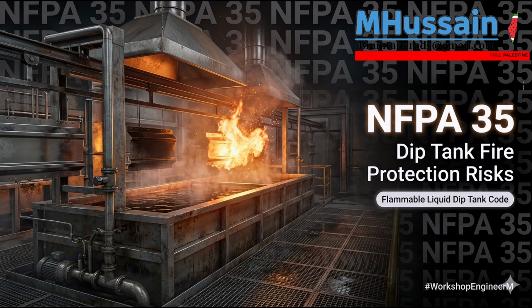Okay. To the maintenance team and the plant manager, that seems like a massive win. Faster pump equals faster production. Right, they think they just optimized the process. But they haven't consulted the safety engineers. By physically increasing the flow rate, the velocity of the liquid through the steel pipe is now 20% higher. As we discussed, fluid friction generates static electricity. Oh. By increasing the velocity, you have exponentially increased the rate of static electricity generation. The 25-ohm grounding system that was perfectly mathematically designed to dissipate the static generated by the old flow rate might not possess the capacity to dissipate the massive influx of static generated by the new, faster flow rate.